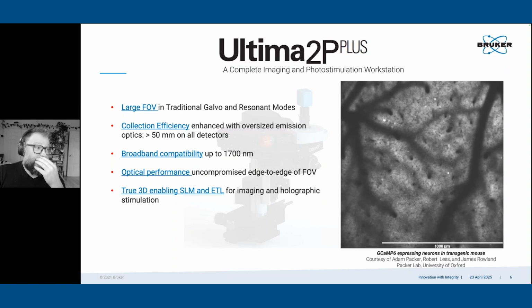So this microscope is developed to have a large field of view and greater collection efficiency, so wider angle of collection, meaning sensitivity is great at deeper tissue levels. It's compatible with longer wavelengths of laser, so it can be done with 3P imaging potentially if you so desire. And it has a good quality field of view, so you have your good image across a wide field with uniformity.